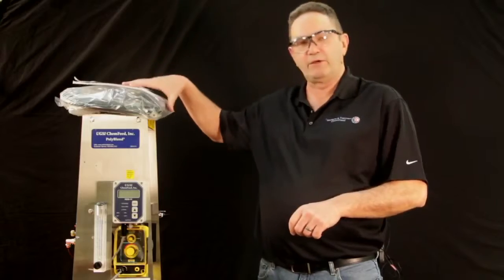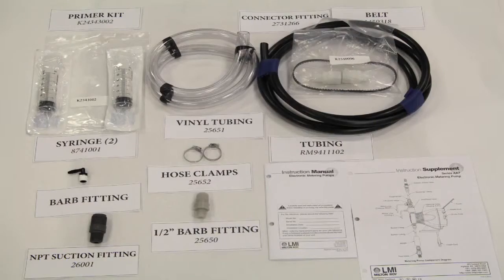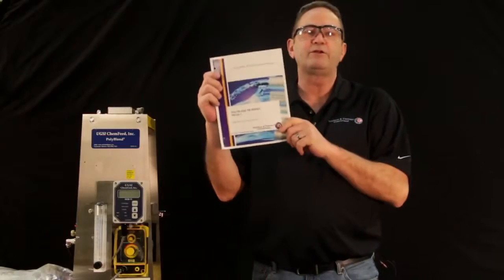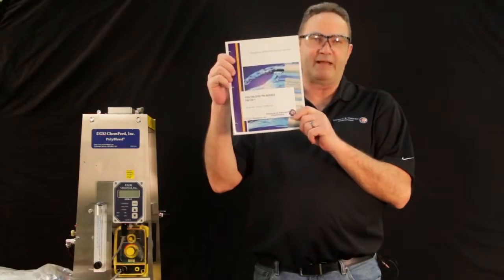When you uncrate it, you will find inside your unit a bag of parts: a priming kit, 2 syringes, barb fitting, vinyl tubing for your polymer, connector fittings, and a spare belt, tubing for your solution discharge, hose clamps, NPT suction fitting, a 1/2-inch spare barb fitting, and your instruction manual for your neat polymer pump. And your user and maintenance manual. These are very helpful hints for you.